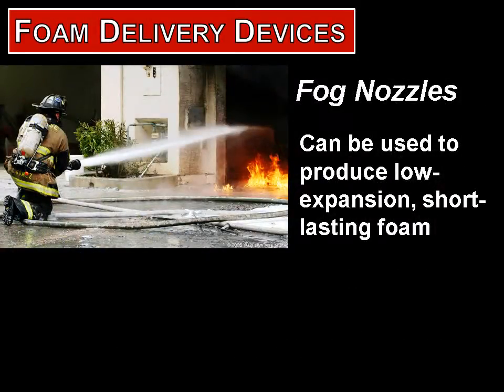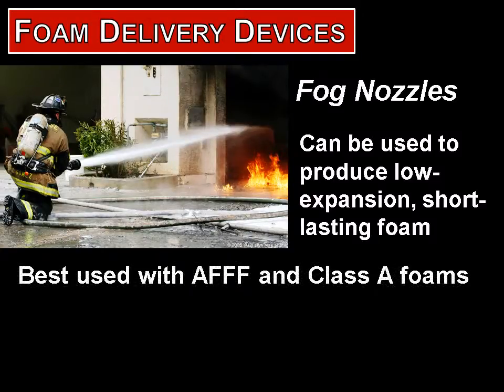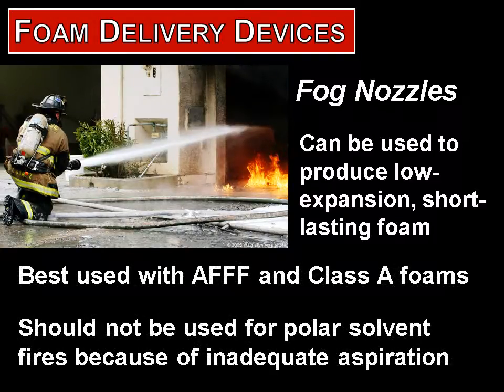Fog nozzles can be used to produce low expansion, short lasting foam. Best used with AFFF and Class A foams. Should not be used for polar solvent fires because of inadequate aspiration, which means you're not getting enough air into your foam to create the bubbles and the blanket that you're going to need.